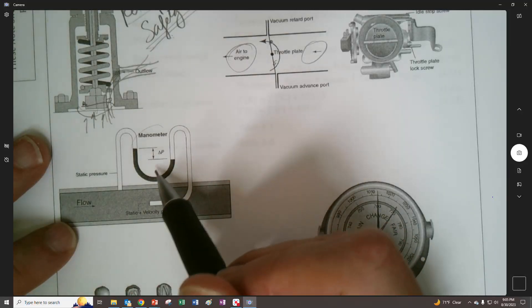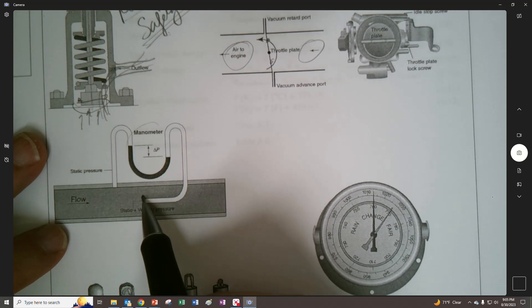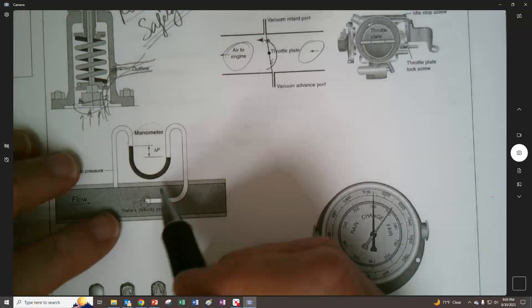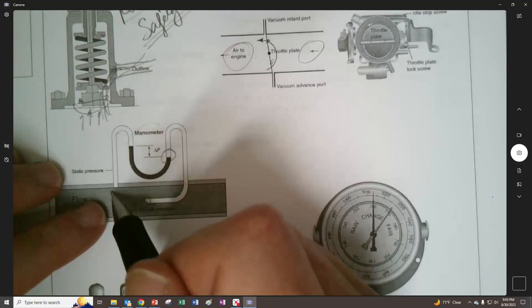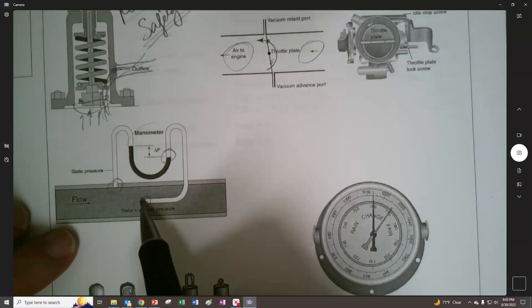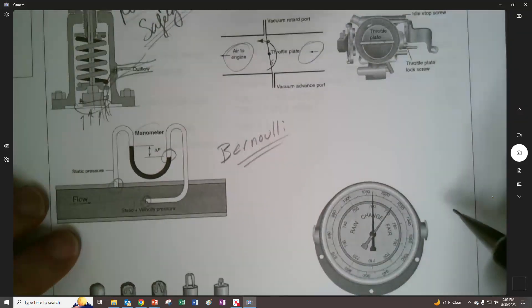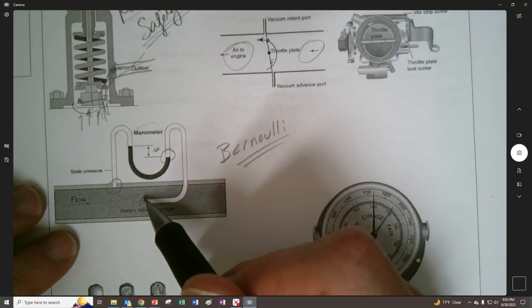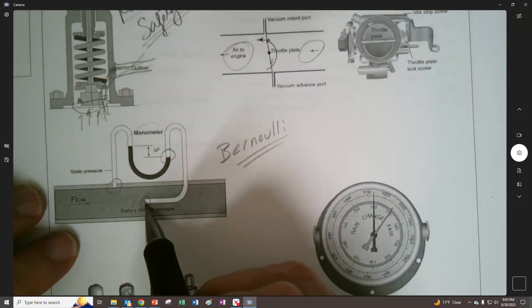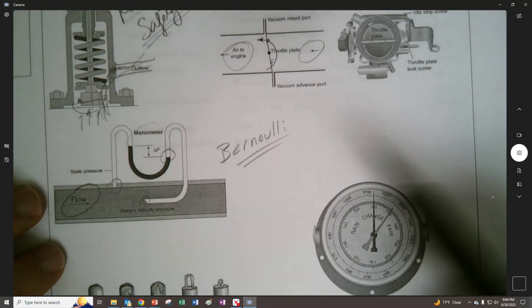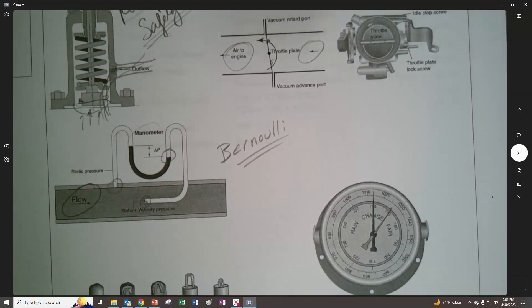Here is using a manometer, it's an application of a manometer. This works as a flow meter, right? So what we're able to do is we're able to get what the pressure is, we call this the stagnation pressure. So we have flow coming through here and we kind of stop the fluid which kind of like raises the pressure. We take some of the velocity energy and turn it into a pressure energy which makes this side greater than that side. We also like make a comparison so it's like this pressure versus that pressure and what we could do is work it backwards using our good friend Bernoulli. Bernoulli's equation is a classic energy equation used in fluid mechanics, fluid dynamics. Very, very useful. It could be overused but it's a very useful thing but by that principle is what we're able to work backwards, figure out what the velocity is and now we can calculate what the flow is because we have this pressure drop. So this is a flow meter of sorts. It's not the most precise thing in the world but it does a good job.